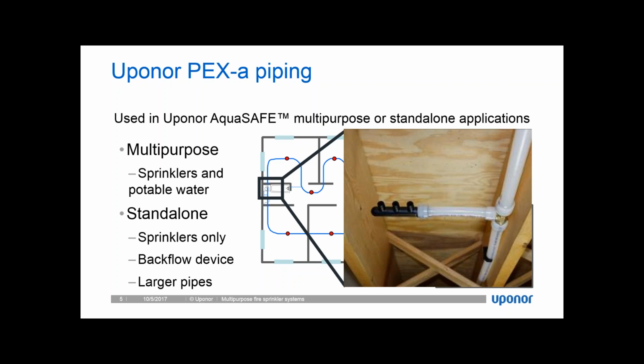Now this contrasts a different type of system that is primarily installed in the United States, which is called a standalone system. Standalone systems use piping for sprinklers only. Now, because you're using piping for sprinklers only, you're going to need to put some sort of check valve or double check valve or some other type of backflow prevention device on that system to prevent the yucky water from mixing with the yummy water. Okay, so we don't want any of the sprinkler water to mix with the potable water. And that can happen in the house where that separation occurs. And sometimes they bring a separate line all the way out to the street and still put a check valve or some sort of backflow prevention device on that to make sure that the sprinkler water doesn't get back into the municipality water.